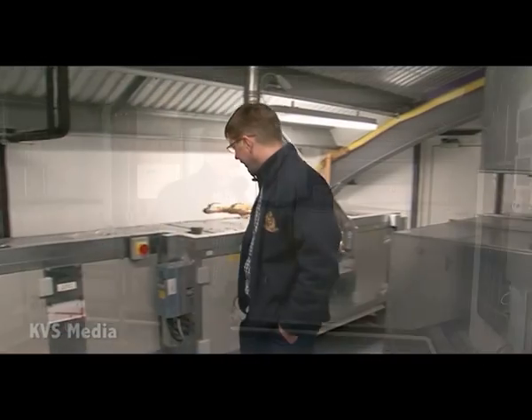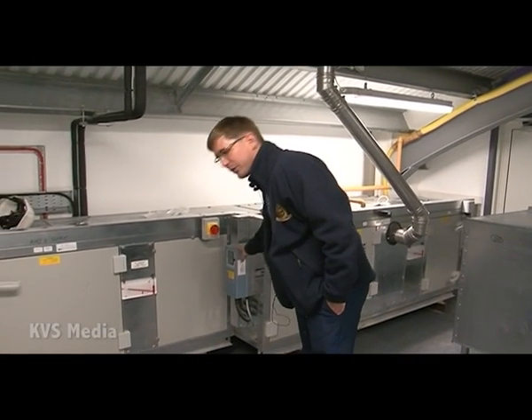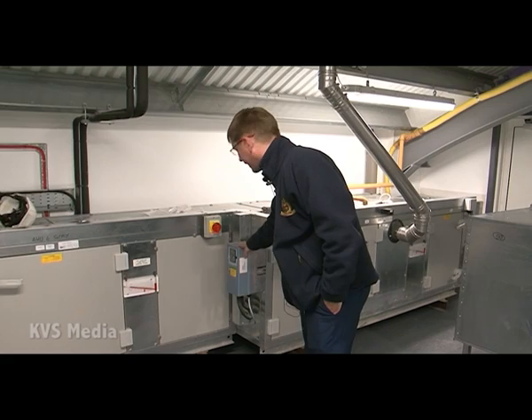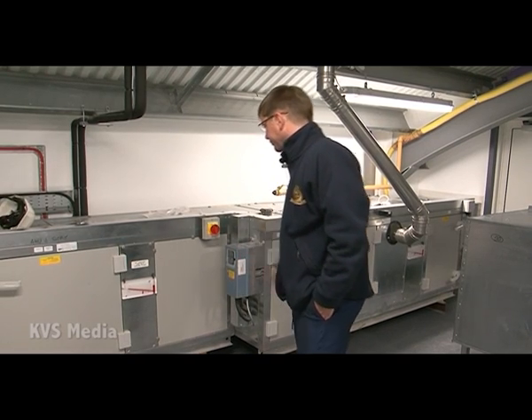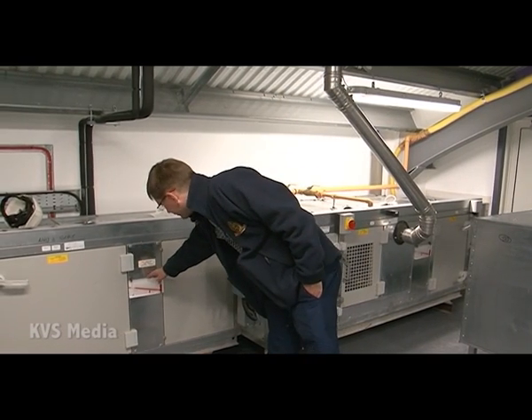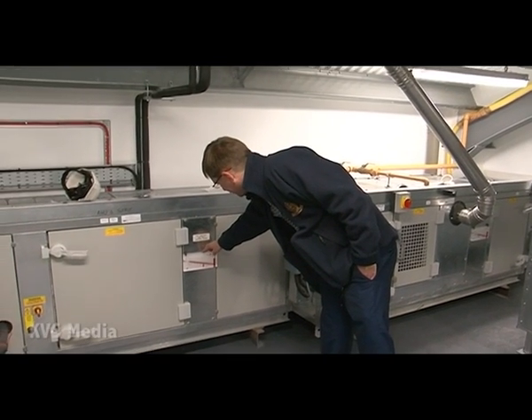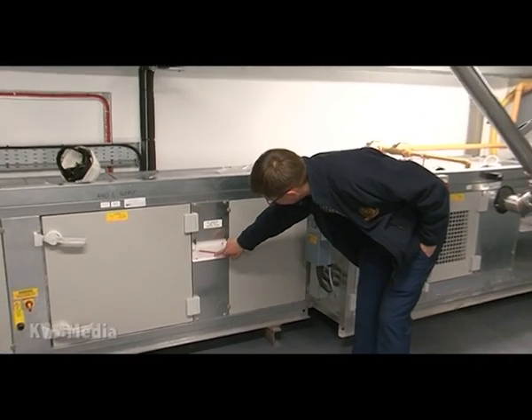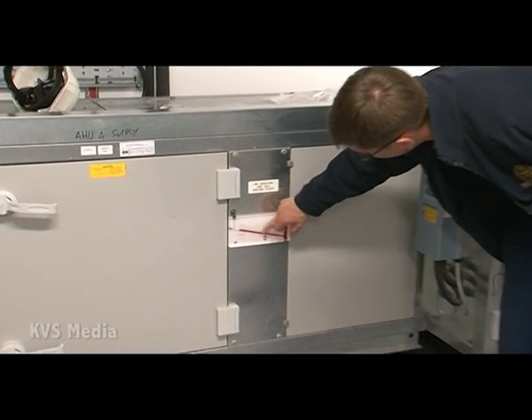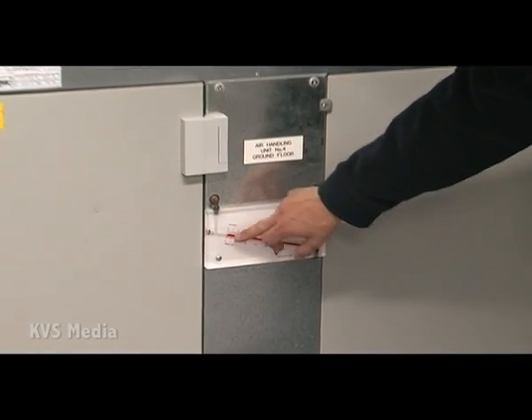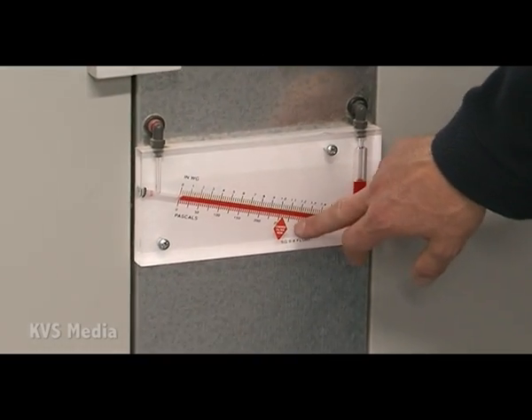The extract air is then drawn through the atrium from the classrooms and everything via crosstalk attenuators and the linear grills. Here we have the inverter speed controller for the air handling unit, and also here is the gauge for the filters. The red indication here is when the filter is dirty and needs changing. So at the moment that's currently showing that the filter is in need of changing, which we will be doing shortly.